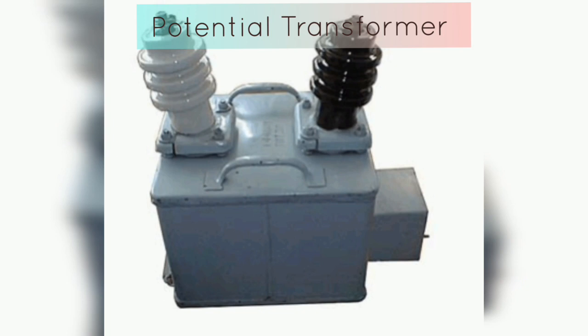A potential transformer (PT) is a type of instrument transformer used to measure high voltage levels in power systems. PTs work on the same principle as current transformers, using electromagnetic induction to provide a reduced voltage output proportional to the original voltage. The primary winding of a PT is connected in parallel with the conductor carrying the high voltage to be measured. The secondary winding is connected to a measuring instrument such as a voltmeter or relay, and provides a reduced voltage output proportional to the original voltage. The ratio of primary to secondary windings determines the amount of voltage reduction.